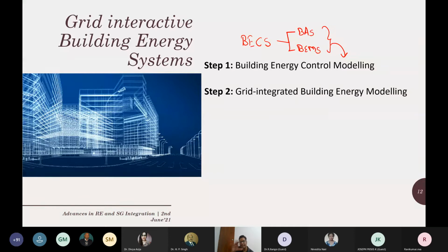The second thing is that you model a building energy system, then you model the control systems, and you work the building energy systems such that if an occupant sets the thermostat to 26 degrees Celsius through a remote control, it has to work. The condenser will keep working, and the mass flow rate will keep giving us cool air unless and until it reaches the tolerance level of the set point value. So you work on the deadband and the PI controller mechanism.